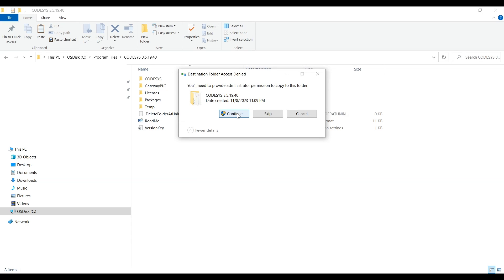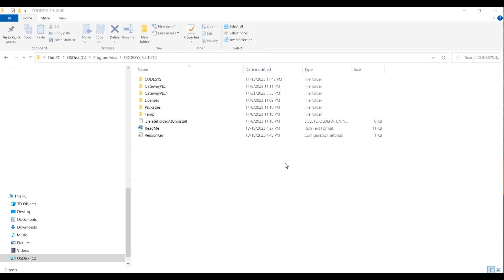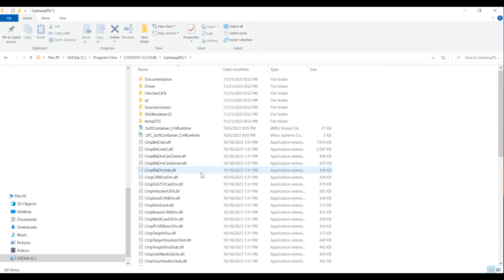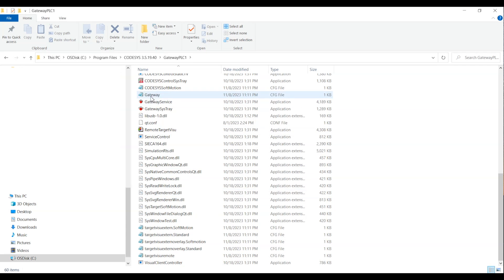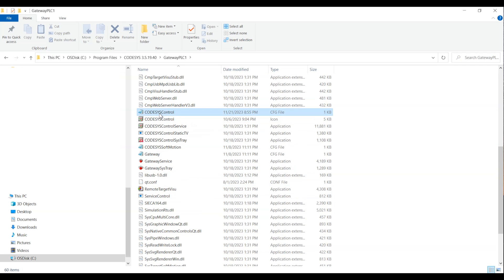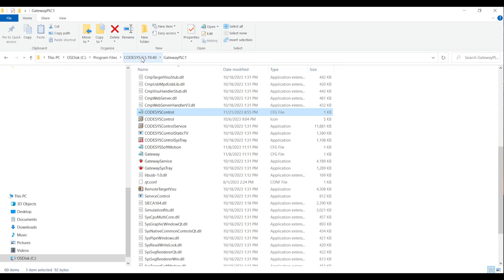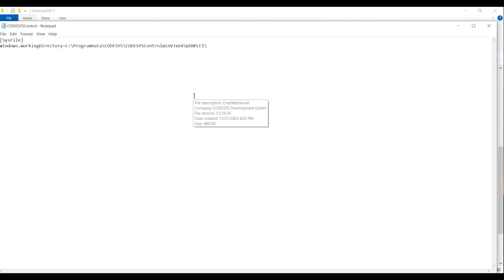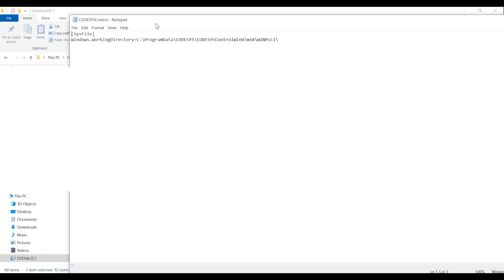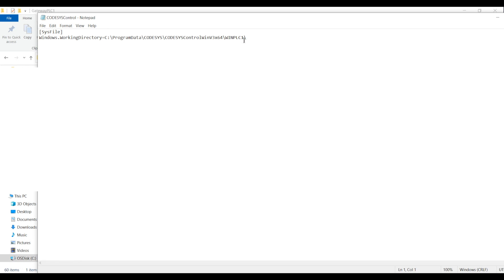When we copy and paste it, give it a different name — I've given it the name 'Gateway PLC One', as you can see. Now, inside this folder, let's look at which service runs and what the configurations are. We have a CodeSys Control configuration where we need to provide the path of the soft PLC folder, which is where all the downloads will happen. In this file, you can see we have a 'working directory' field which we need to configure, and it is located in Program Data > CodeSys > CodeSys Control for Windows WinV3x64.